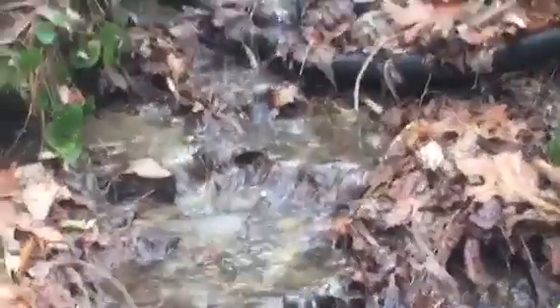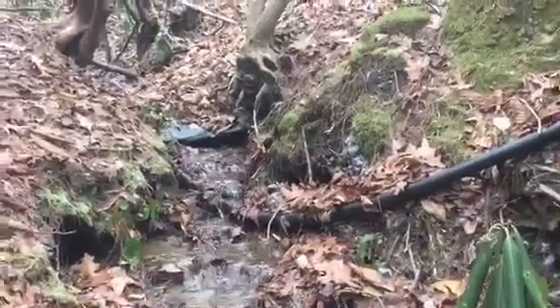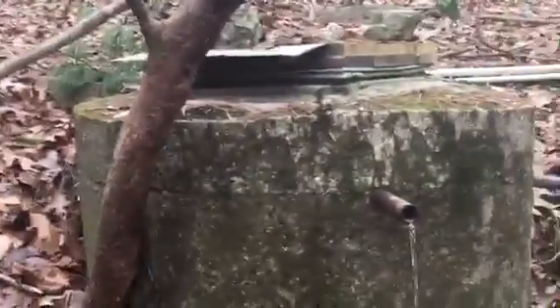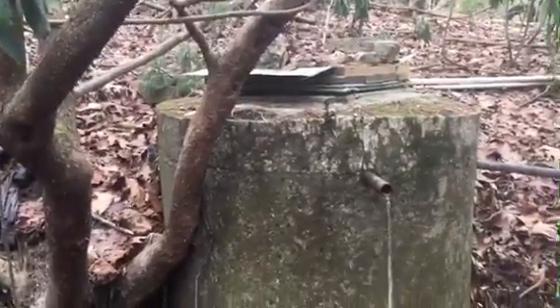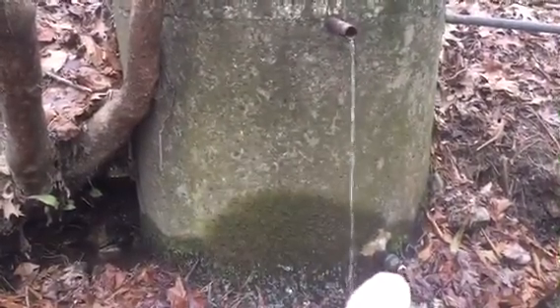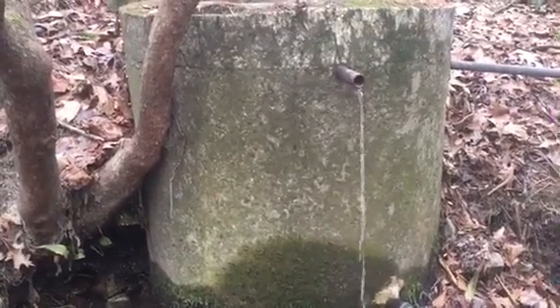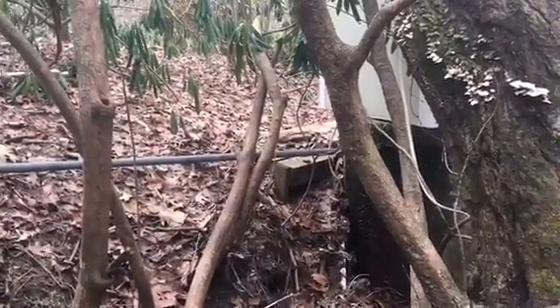You can see the water flowing out — there's a pile of water coming out, and it is all spring water. There is no creek or anything flowing. There is the black line — we are about 30 feet below that spring box. You can see the black HDPE pipe going in; it goes into this first cistern. Right above the hill was the first house, an old homestead. They had a lid on the top — that's where they would pump from. The pipe comes in on the left-hand side; that is the water level inside. They also have a drain at the bottom. We drain these out every year and keep washing sediment out. I'm using both of these as sediment catchers — so there's the first one. Once it comes up to the overflow, it goes out this pipe here and into the second one.